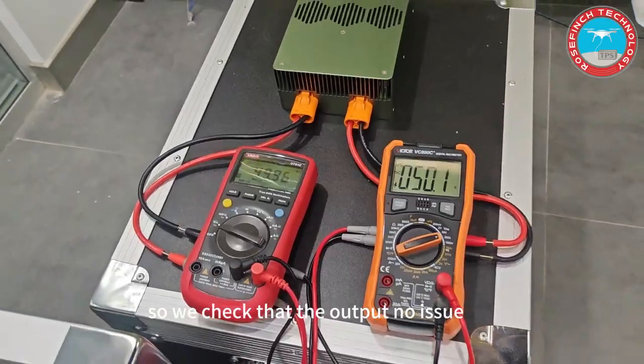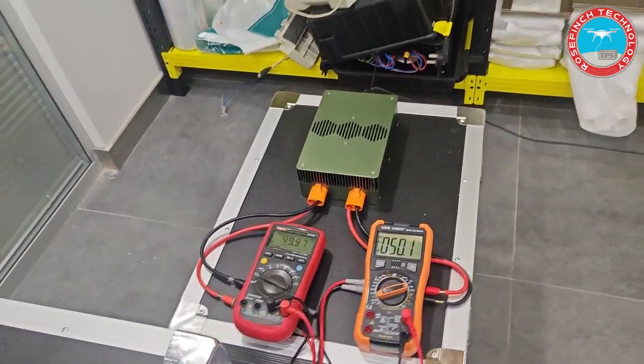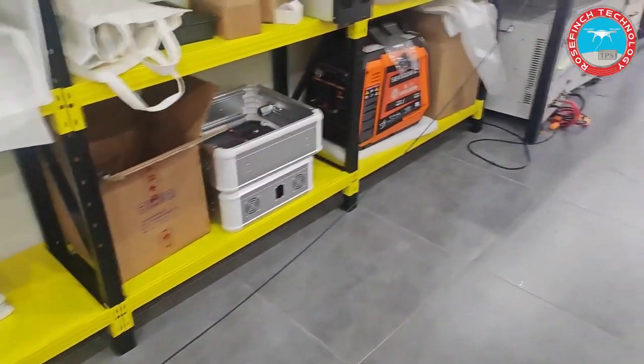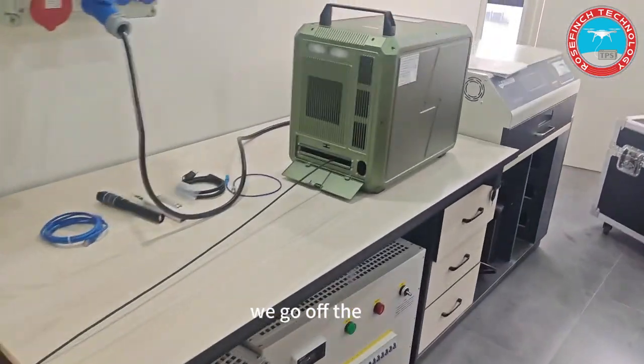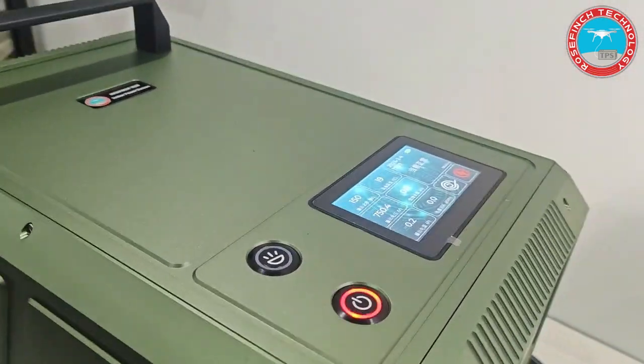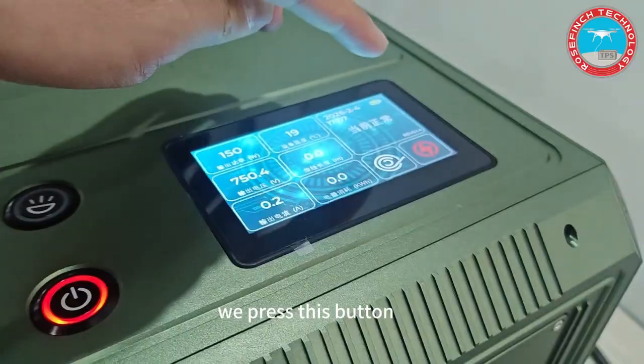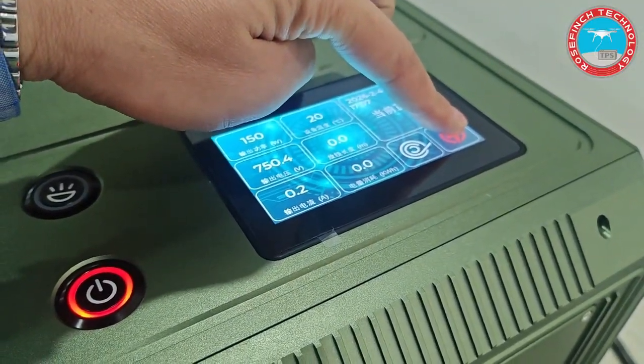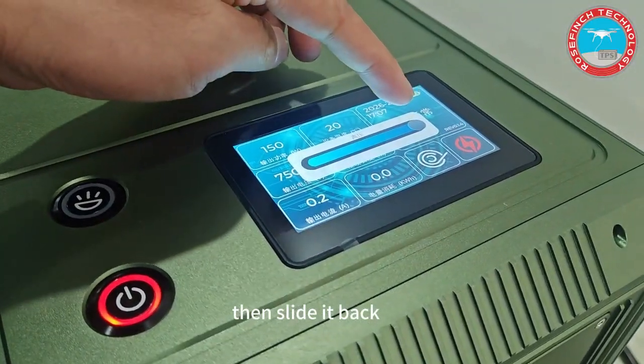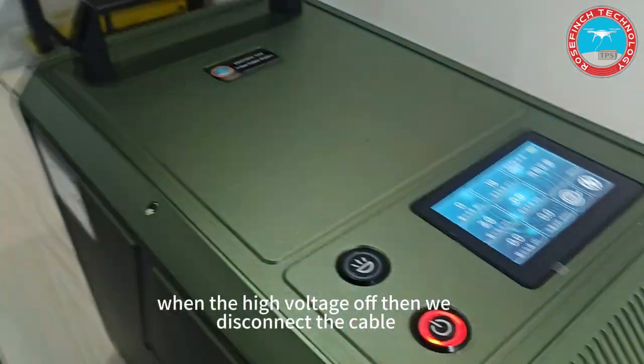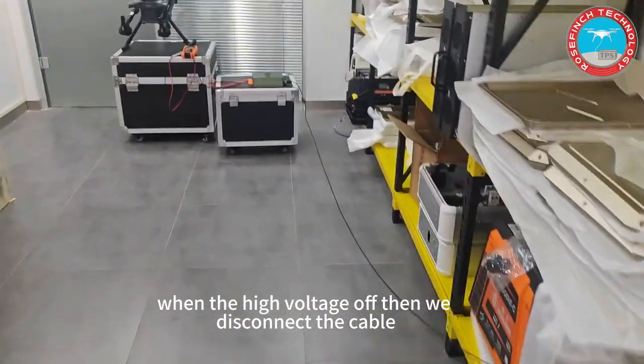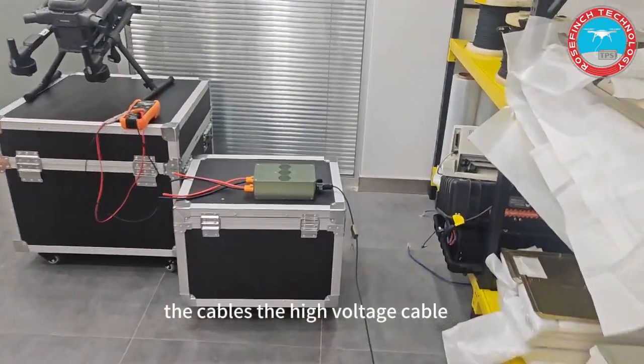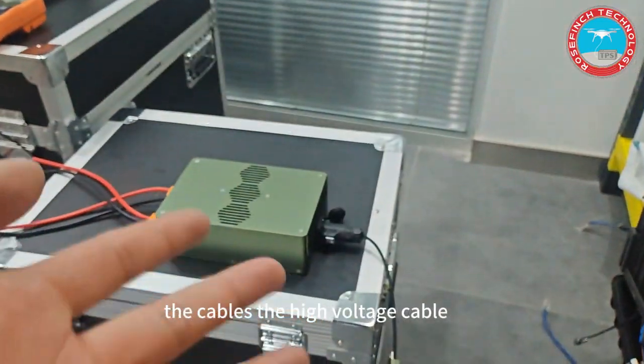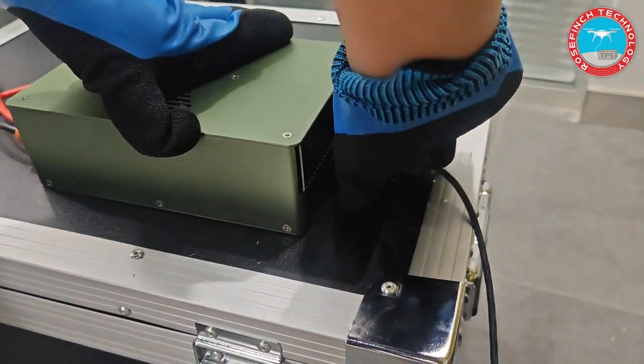So we check that the output has no issue. Then we will turn off the high voltage. We press this button, then slide it back. When the high voltage is off, we disconnect the cables, the high voltage cable connector. Yes.